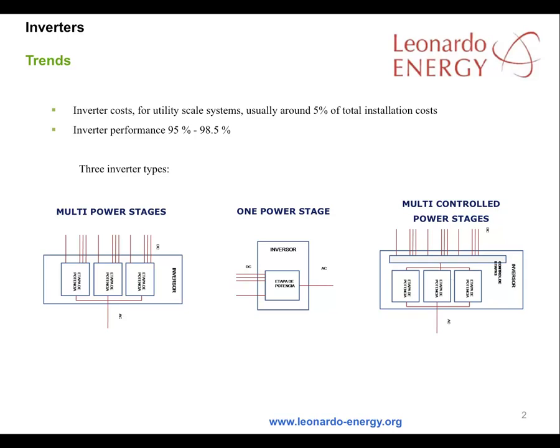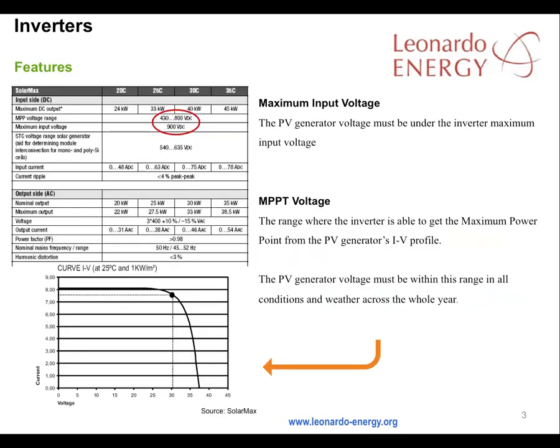The electricity company that your solar plant supplies will be concerned about the potential effect of your solar plant on its network. They may ask for galvanic isolation transformers where the connection is low voltage. The main issues to consider when selecting the inverter include the maximum input voltage — that's the voltage of the PV generator — which must always be below the inverter's maximum input voltage.